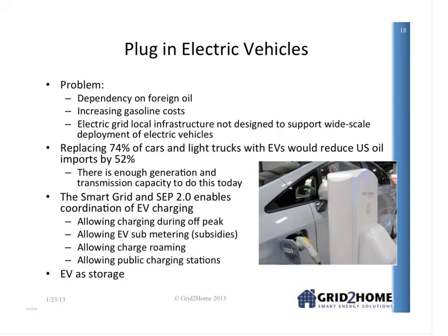And there's an estimate we could probably power the majority of electric vehicles without any increase in the energy, and without building any power plants, as long as you charge them at night. There is a local problem with your distribution transformer, but not from the generation capacity side of it. I don't know if you know, in the US, there's a transformer that sits on your house, and there's about 5 to 7 homes that that one transformer feeds. Okay? An electric vehicle can look like about 4 homes at a time. So a transformer can take a short period of time when it can be overloaded. It's got some heat inertia in it, can feed one vehicle.